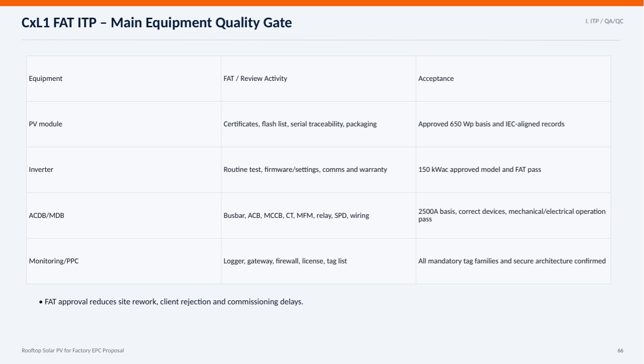Next, the ACDB and MDB components are checked for busbar quality, circuit breakers, relays, wiring, and other electrical elements. Acceptance requires a 2,500 ampere basis with confirmed mechanical and electrical operation. Finally, monitoring and power plant controllers must have validated loggers, gateways, firewalls, licenses, and tag lists, ensuring all mandatory tag families and secure architecture are in place. Approving these FAT processes early on significantly minimizes site rework, client rejection, and commissioning delays, ensuring a smoother project delivery.